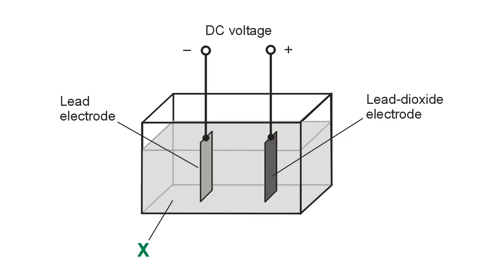2 of them. And you have to be careful with batteries like this, because sulfuric acid, the chemical formula for that is H2SO4, and the H2 is one bugaboo with this stuff. The hydrogen can bubble out of a battery like this, or a cell like this, particularly if it gets overcharged. If you overcharge a cell like this, you get hydrogen gas bubbling out of it, and that can present an explosion hazard.